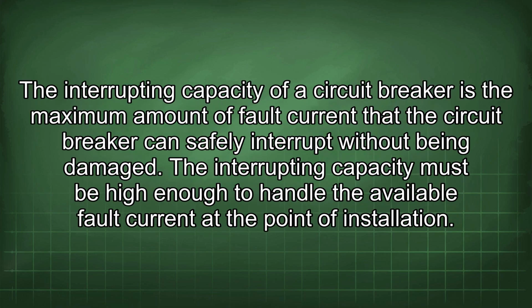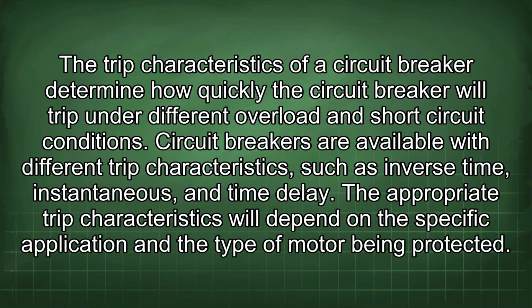The interrupting capacity of a circuit breaker is the maximum amount of fault current that the circuit breaker can safely interrupt without being damaged. The interrupting capacity must be high enough to handle the available fault current at the point of installation. The trip characteristics of a circuit breaker determine how quickly the circuit breaker will trip under different overload and short circuit conditions. Circuit breakers are available with different trip characteristics, such as inverse time, instantaneous, and time delay. The appropriate trip characteristics will depend on the specific application and the type of motor being protected.